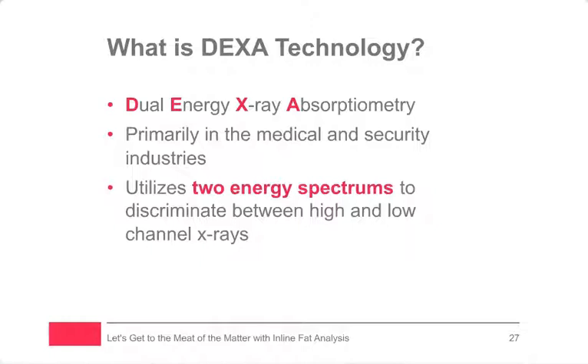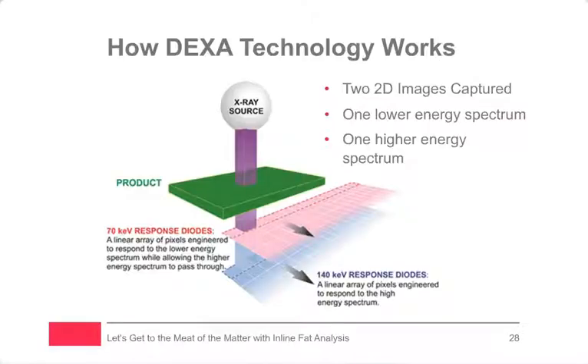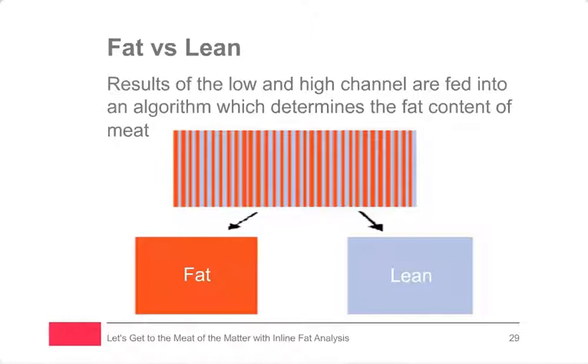Well, what is DEXA? DEXA is a technology that's been used in the medical and security industries for some time. It utilizes two energy spectrums to discriminate between high and low X-ray channels. What this means is we actually have two separate diode arrays, and they are separated by a metallic shield. The metallic shield means that only high-level energy X-rays will pass through to the high-level or 140 keV response diodes. This means that at each individual diode location, we can look at the ratio between the high and the low. By comparing what X-ray output comes from the two diodes, we can compare the ratio. And it is this ratio which allows us to determine what is fat and what is lean.